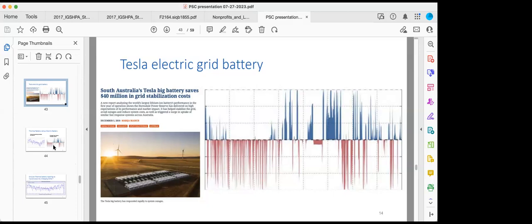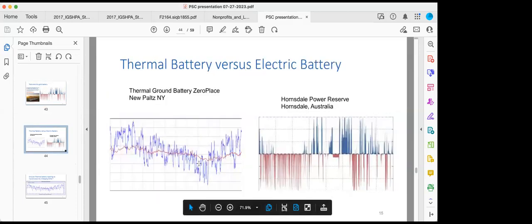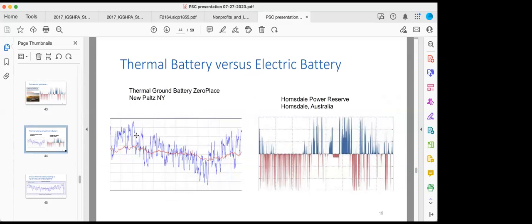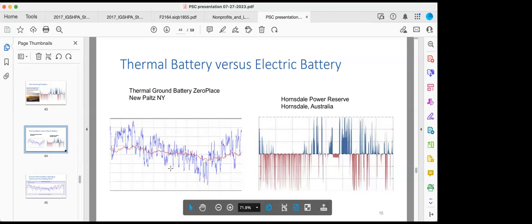Now, look at the loop field here, this is the loop field temperature on an average day in spring. The blue line is the supply temperature into the loop field, and the red line is the entering water temperature from the loop field. You can see the building fluctuates depending on the time of day, whether it takes energy out of the loop field or puts energy into it.